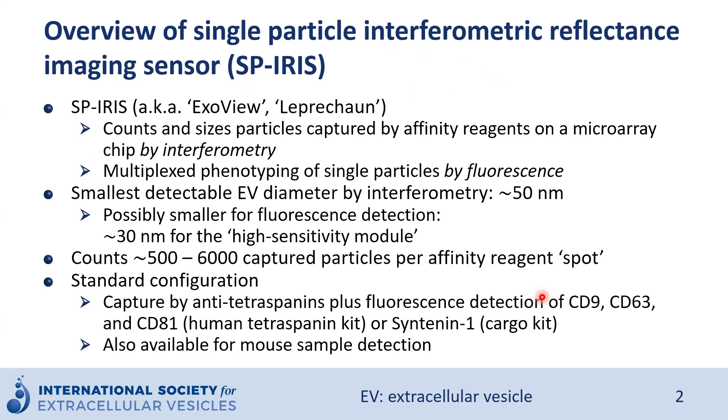SP-IRIS, also known by the brand names ExoView or Leprechaun, can count and size particles captured by affinity reagents — usually antibodies — on the surface of a microarray chip by interferometry. Its platform also provides phenotypical detection at the single particle level using fluorescence. The smallest detectable particles by interferometry is around 50 nanometers; however, a high-sensitivity module can bring the lower detection limit down to 30 nanometers.